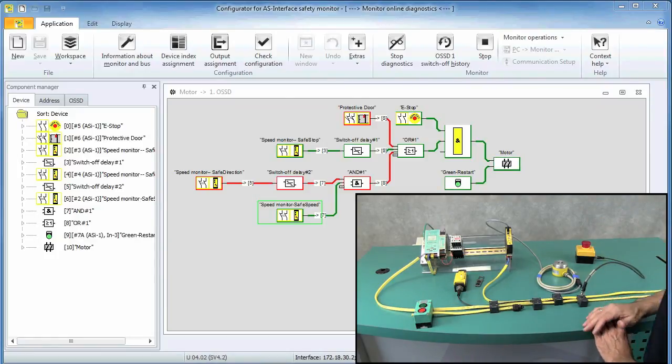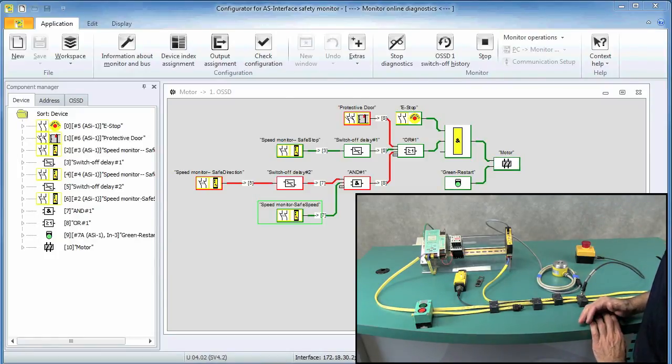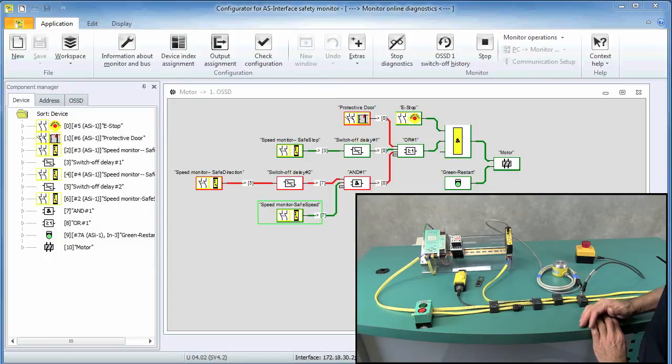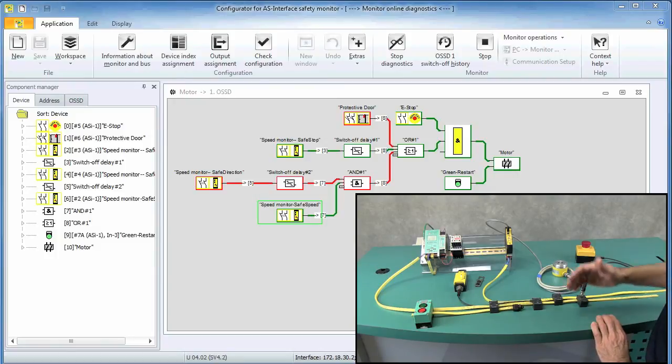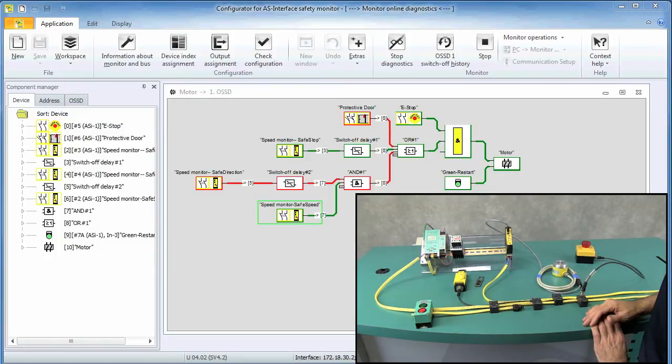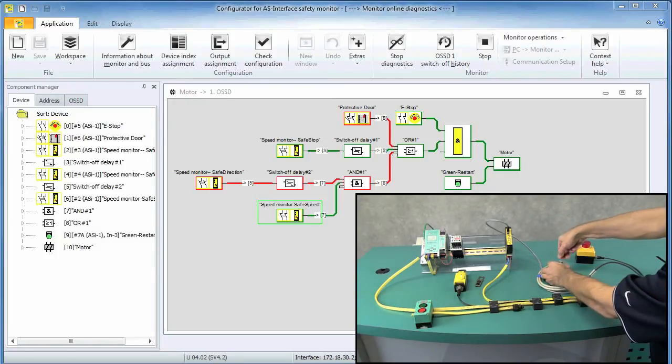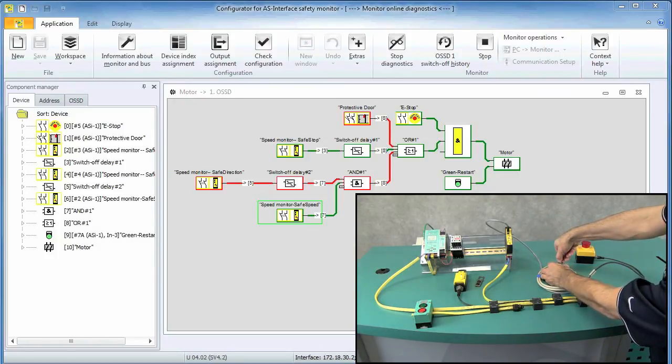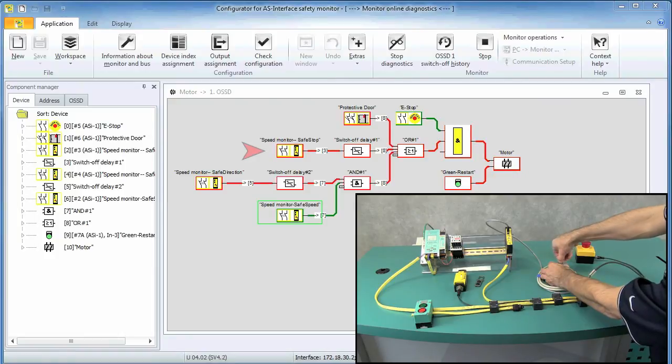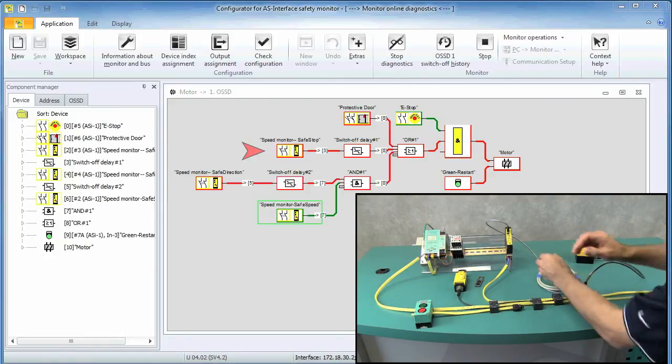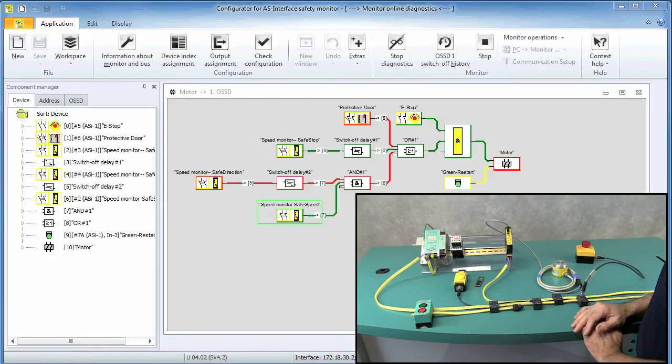So the last operation we need to verify is that when the press moves in the reverse direction, the contactor immediately shuts down. So I will spin the encoder in the reverse direction, which leads to an immediate shutdown.